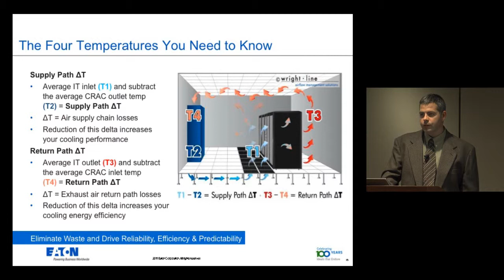So, four very easy temperatures to measure without getting too scientific. But the bigger the delta between the cold air coming out of the supply into the servers, or out of the servers back to the cooling system, the more likely it is that there's something undesirable or something leading to inefficiencies going on within your data center. And so the idea is you want to eliminate that, not only to increase efficiency, but to increase the predictability of your cooling.